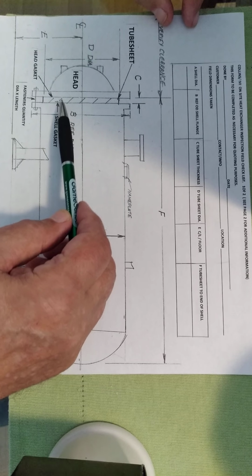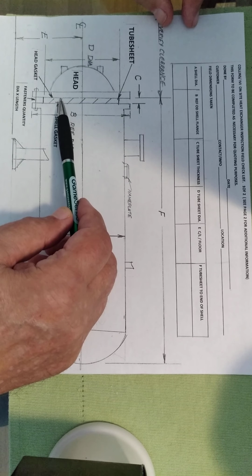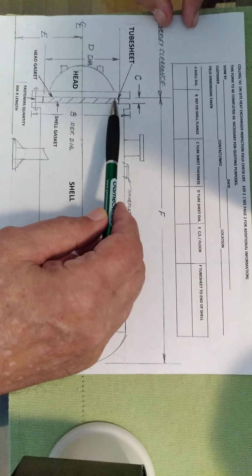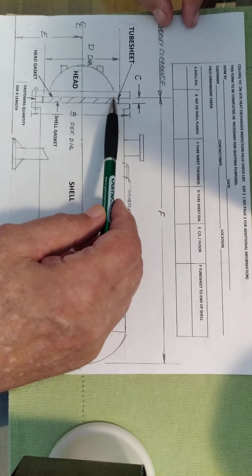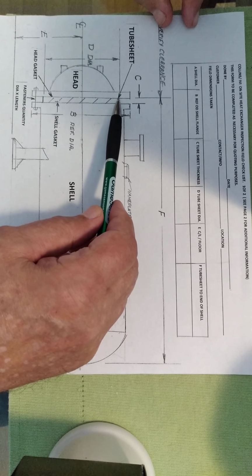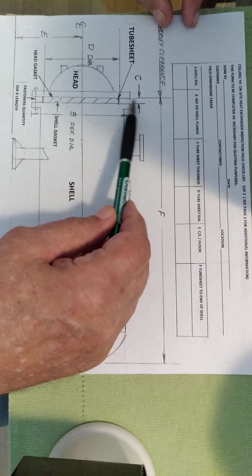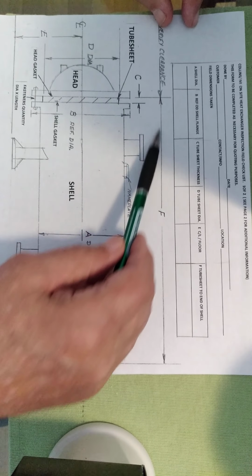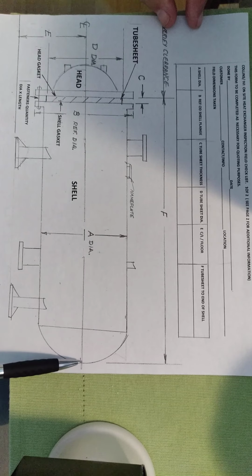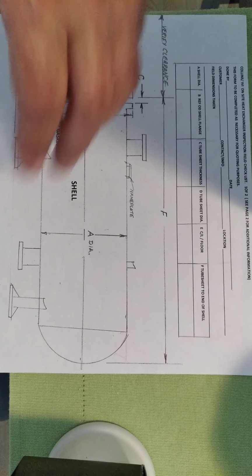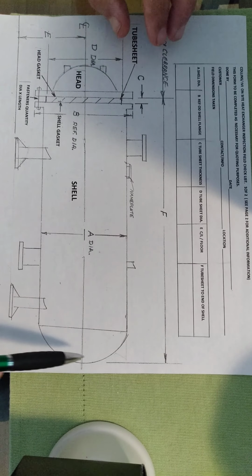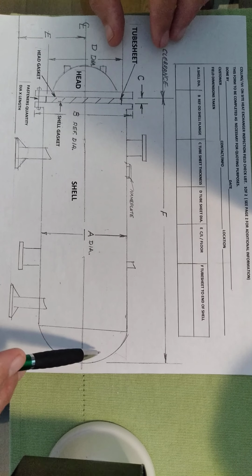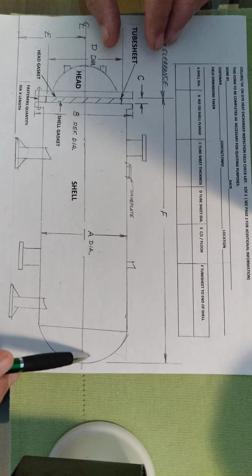And that's not, the tubes actually go all the way through the tube sheet. The tube sheet has the cross hatch lines here, and that's where you want to get the dimension from, this surface right here, where the tube sheet arrow is, all the way to the end of the unit. Now, keep in mind, this may have insulation on there, and even if it doesn't, your tubes are not going to go all the way to the end.